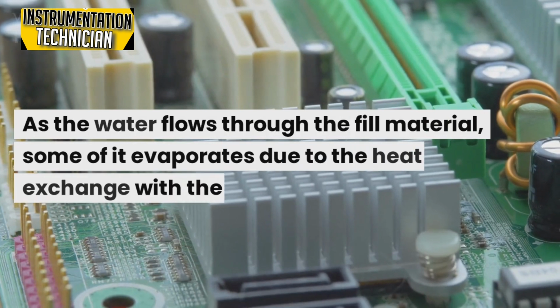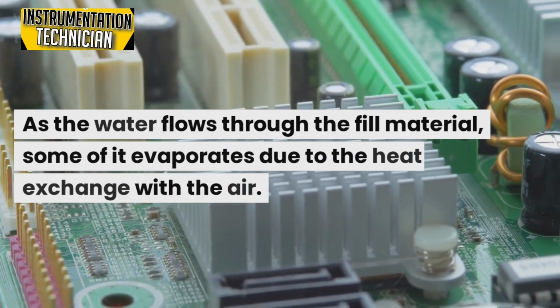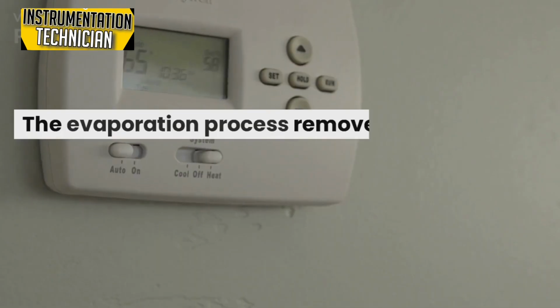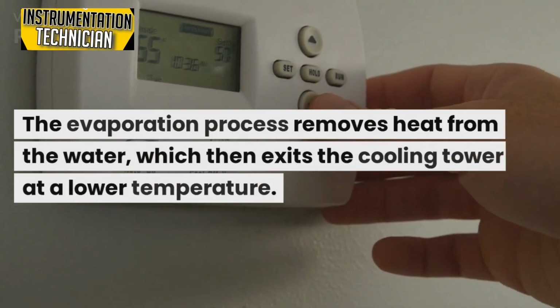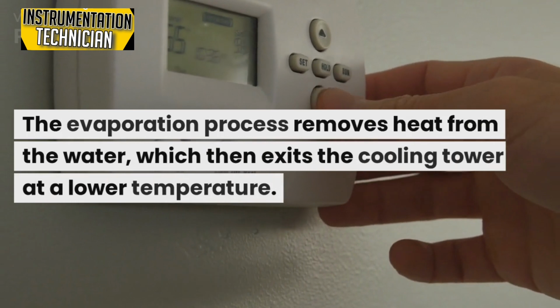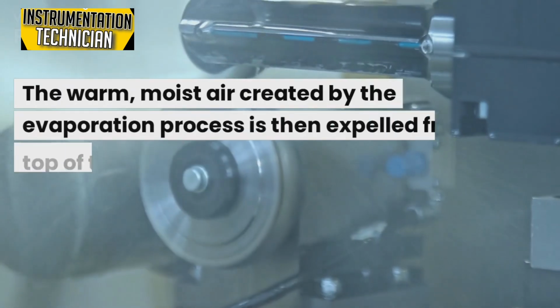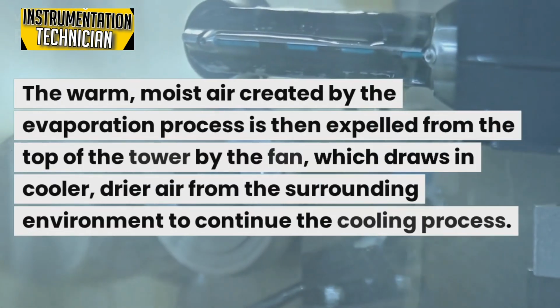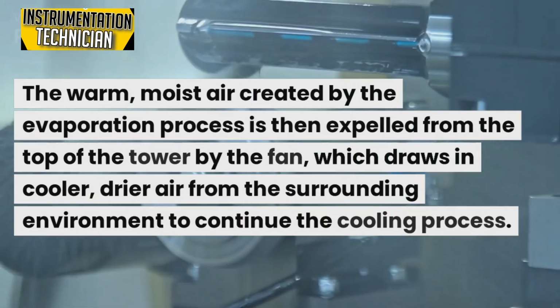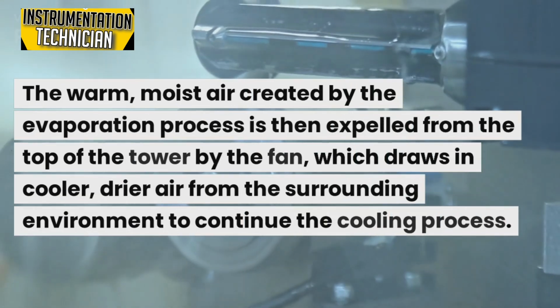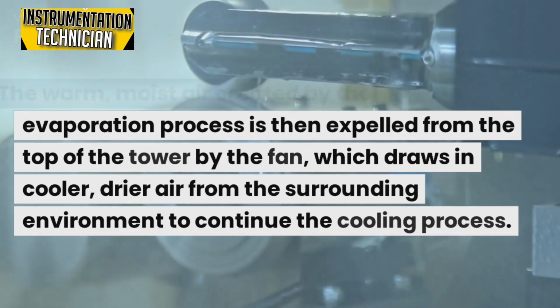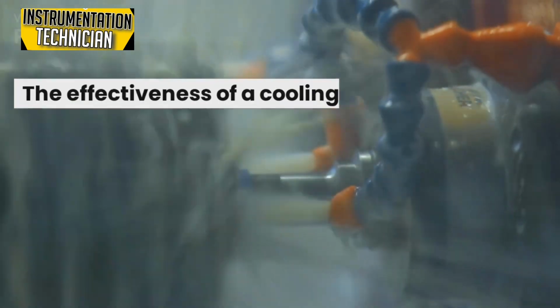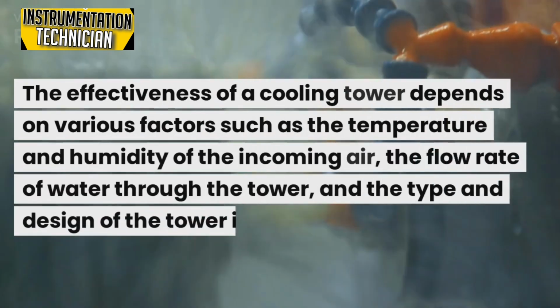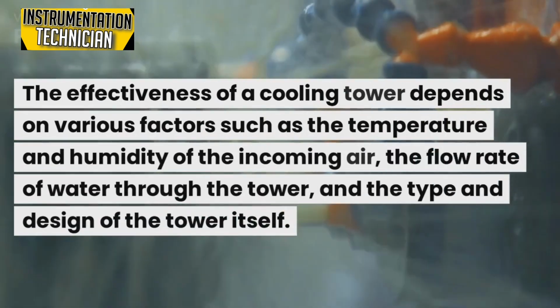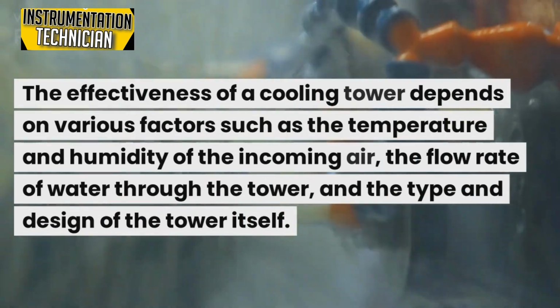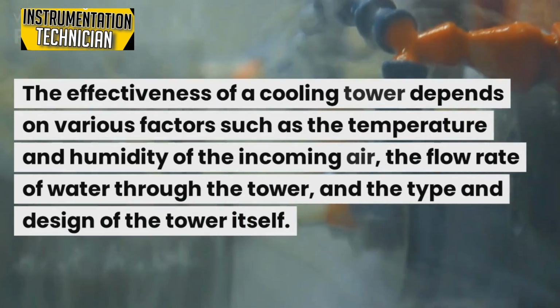As the water flows through the fill material, some of it evaporates due to the heat exchange with the air. The evaporation process removes heat from the water, which then exits the cooling tower at a lower temperature. The warm, moist air created by the evaporation process is then expelled from the top of the tower by the fan, which draws in cooler, drier air from the surrounding environment to continue the cooling process. The effectiveness of a cooling tower depends on various factors such as the temperature and humidity of the incoming air, the flow rate of water through the tower, and the type and design of the tower itself.